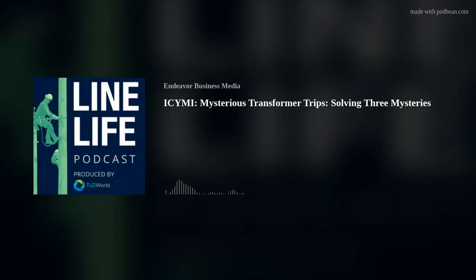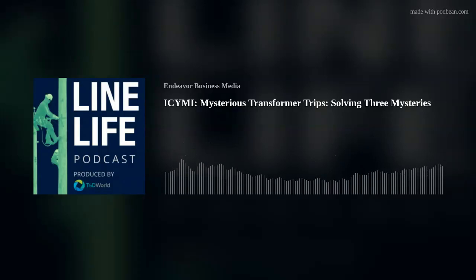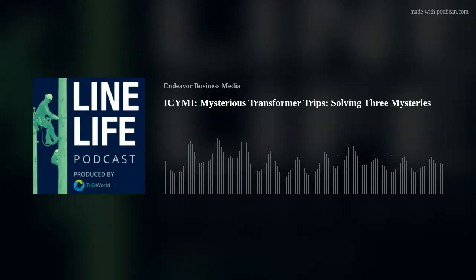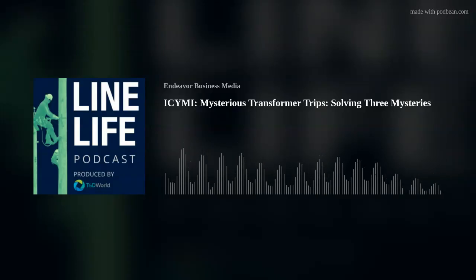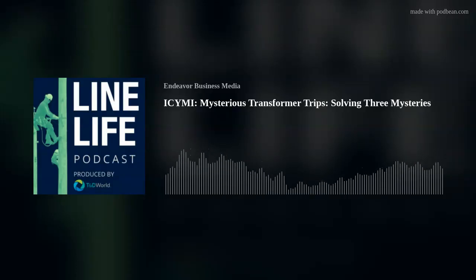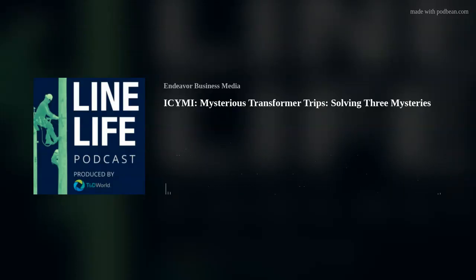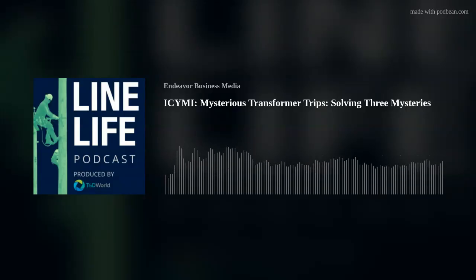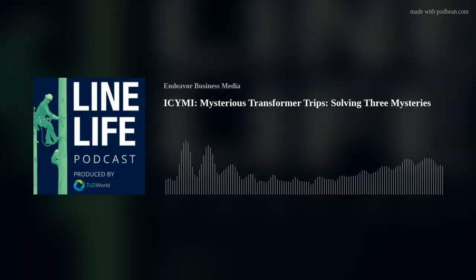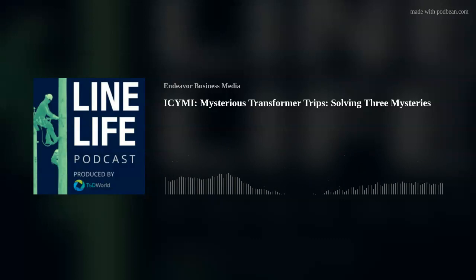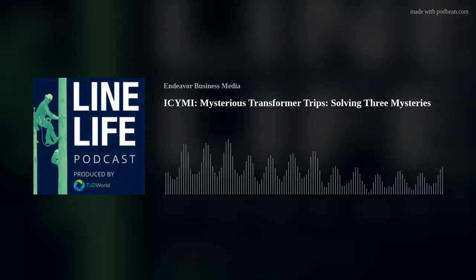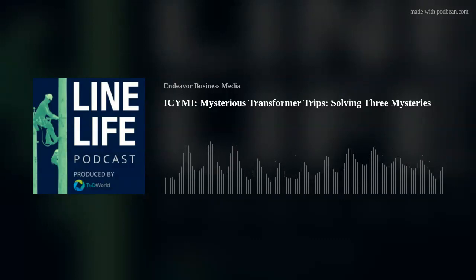A mind of its own. In this final story, a transformer tripped on an 86T relay operation that opened the SF6 breaker ahead of the transformer and tripped the secondary main in a separate E-house. Keeping with the theme, the strange part was no targets to help explain what caused the operation. A review of the drawing showed several items that could operate the 86T relay: transformer differentials, low gas pressure in the SF6 breaker, and the sudden pressure relay.